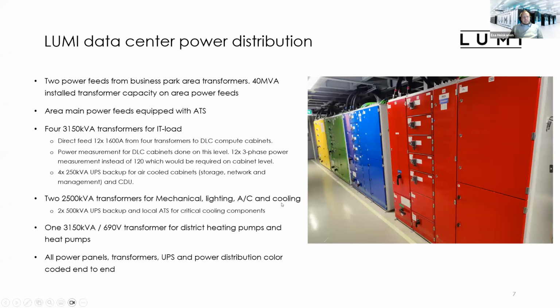So then, in the LUMI data center power distribution, we have 2 power feeds from the business park area transformers, and there is 2 times 40 MVA of installed transformer capacity in these 2 power feeds. So there is an ATS in place, and we have 4 transformers of a little bit over 3 megawatts for the IT load. This is divided so that we have twelve 1600 amp direct feeds from our 4 transformers to direct liquid cooled compute cabinets. So there is no backup power in place.